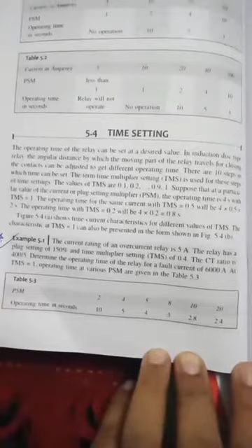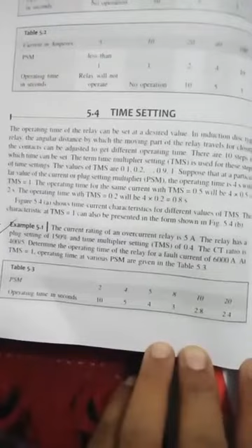So a similar numerical is there in the textbook, in which you can see the current rating of the overcurrent relay is 5 amps. Relay has a plug setting of 150% and a time setting multiplier TMS of 0.4. CT ratio is 400/5. Determine the operating time of the relay for a fault current of 6000 amps. At TMS of 1, operating time at various PSM is given in the table. So a tabular column is given showing PSM and operating time in seconds.